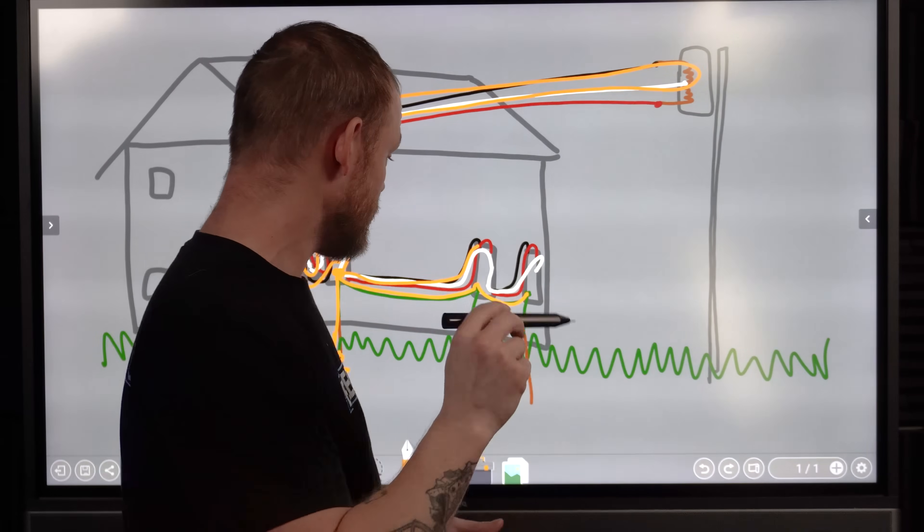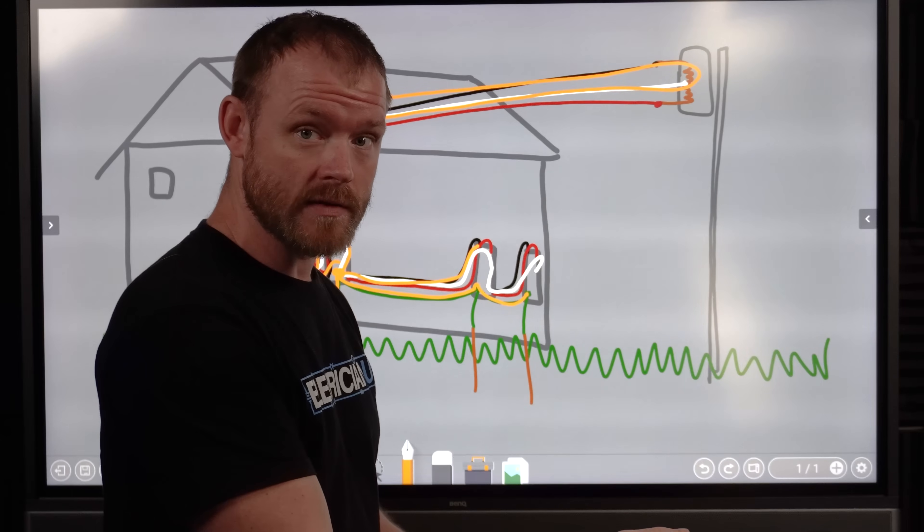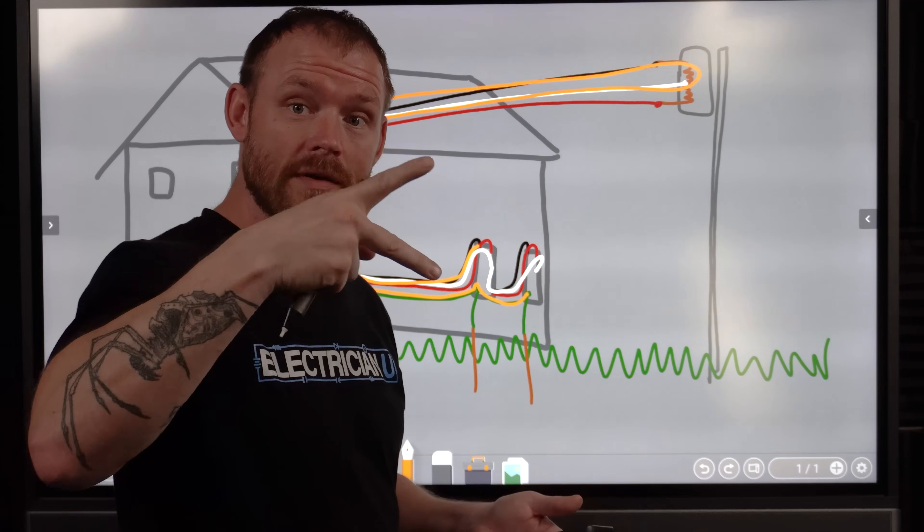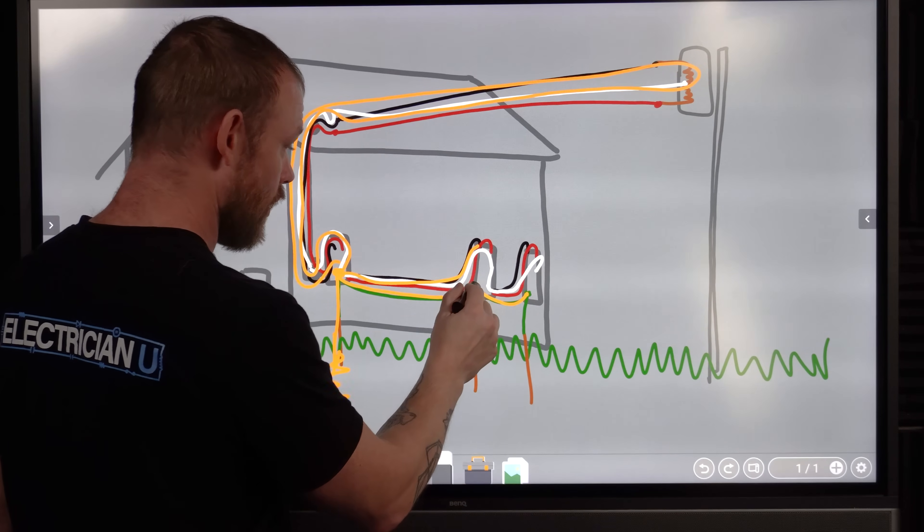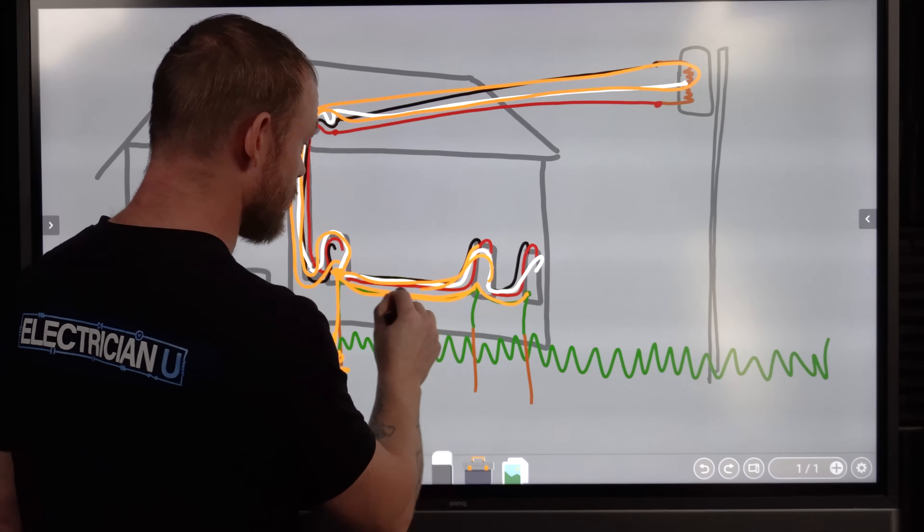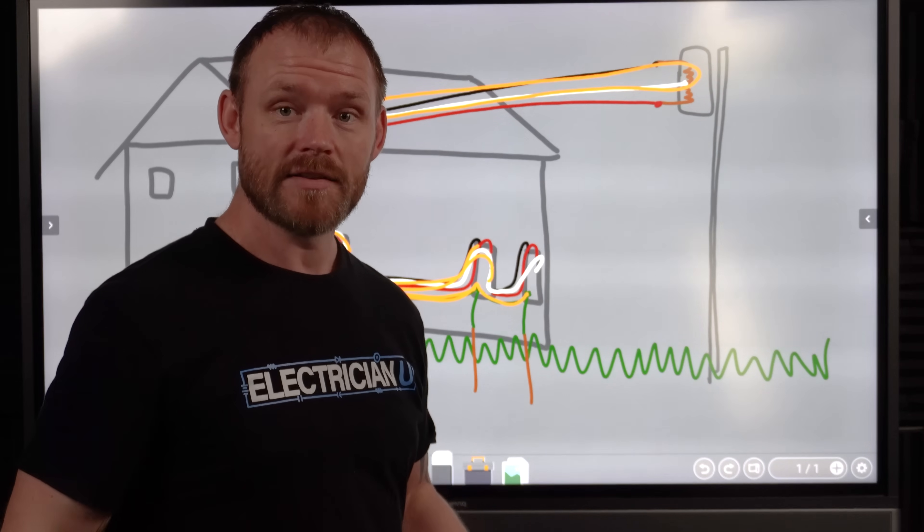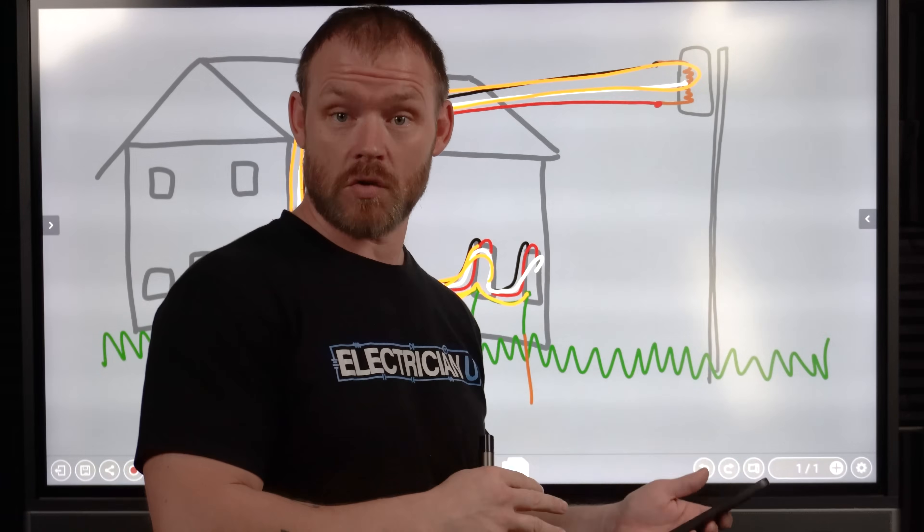Where it becomes tricky is you can't bond your ground and your neutral at each one of the panels because that gives you objectionable current potentially. You have two different paths that current can take. You could have a short go through the equipment grounding conductor and go through the neutral. And now the equipment grounding conductor is touching everything metal. So current's always going to take all paths back to source, right?